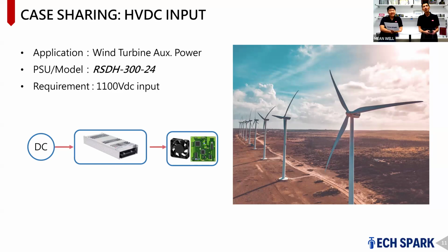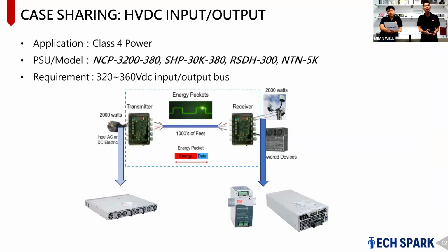All right, let's get to the last one here. We just talked about the Class 4 power, so I'm going to go over it again. What's in the box is the Class 4 power, consisting of a transmitter and a receiver. From transmitter to receiver end, you'll see 320 volt to 360 volt DC, and there's an energy packet coupling that's superimposed on that DC to detect any fault.